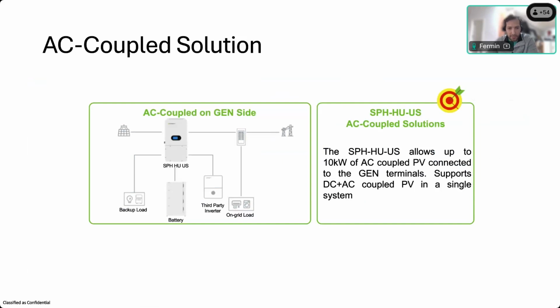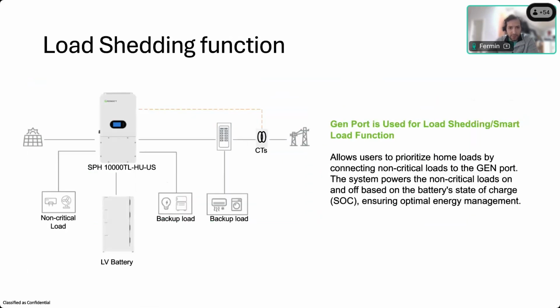There's also a load shedding function. Basically, this function allows you to connect a load to the gen ports as well. This allows you to control a non-critical load in an off-grid case. Once the system reaches a low state of charge that you can easily set in the inverter, this will automatically turn off the non-critical load to avoid further discharging of the battery. This is what the load shedding function looks like. You will connect a non-critical load on the gen terminal ports, and once the battery reaches a low state of charge, the inverter will completely turn off this load and will continue providing power to the backup loads.